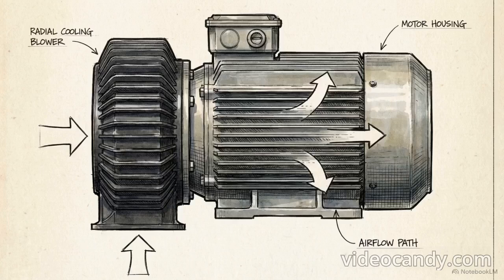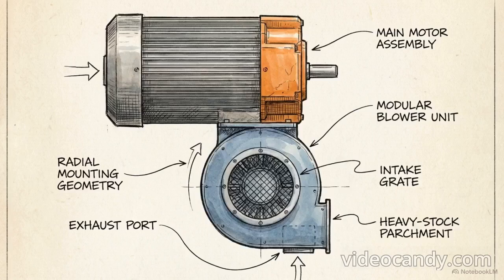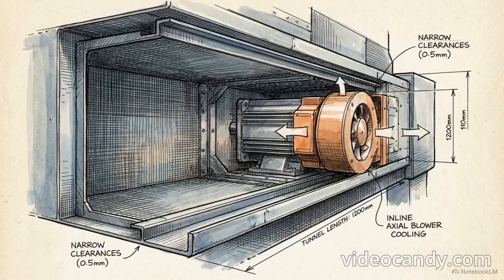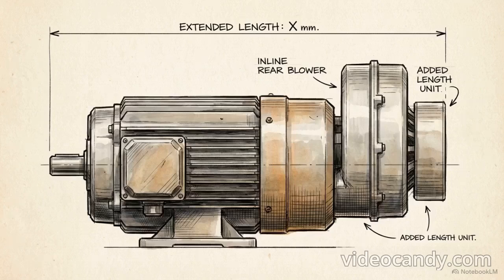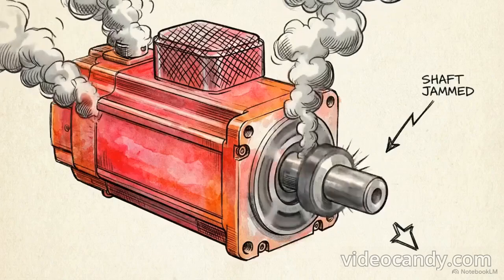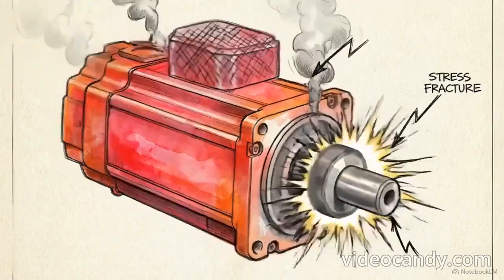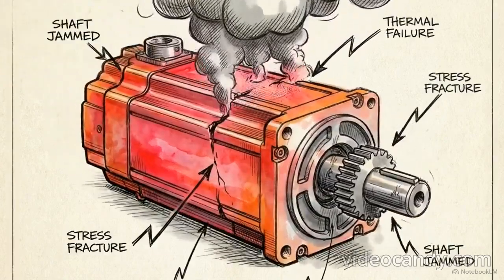Adding these blowers introduces strict geometric constraints to the machine's overall design. When longitudinal space along the shaft is limited, engineers specify radial cooling. This places the blower directly under or to the side of the motor. If the machine profile is narrow, axial cooling mounts the blower in line with the shaft. This keeps the width tight but adds significant overall length to the assembly. The choice of thermal management geometry directly dictates whether a motor survives a continuous heavy-duty cycle or suffers thermal failure.